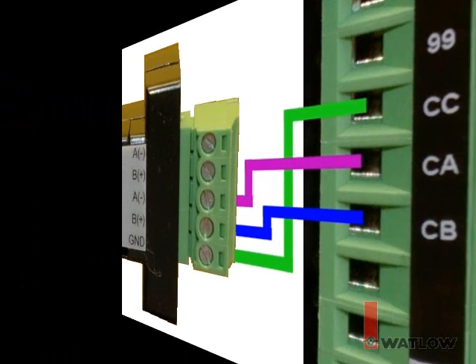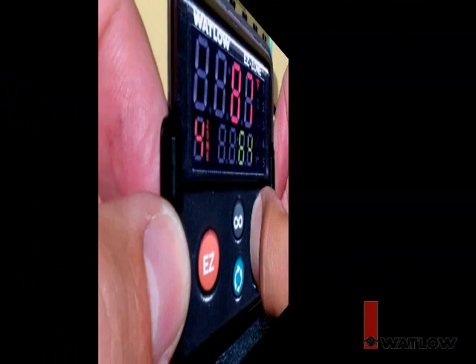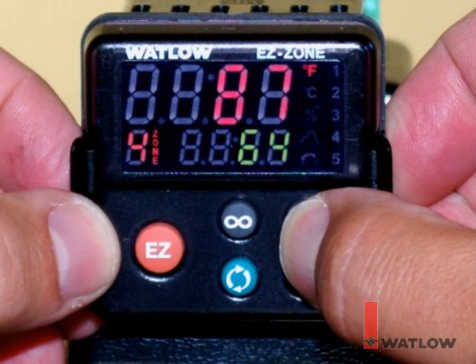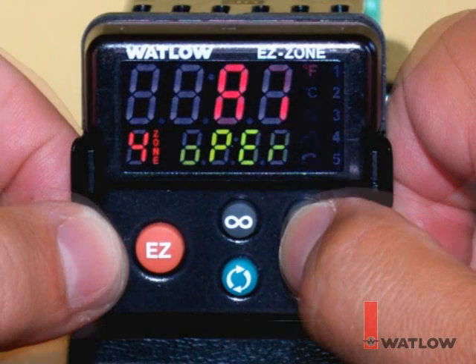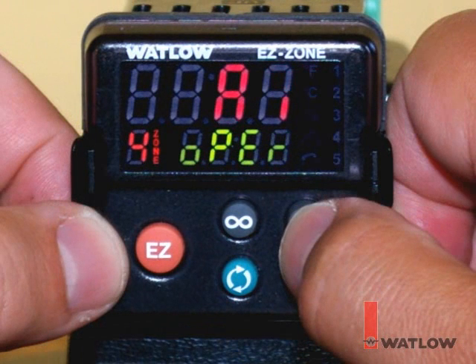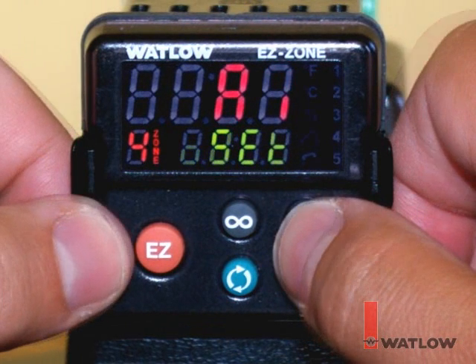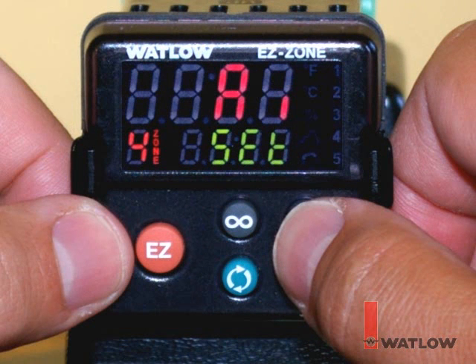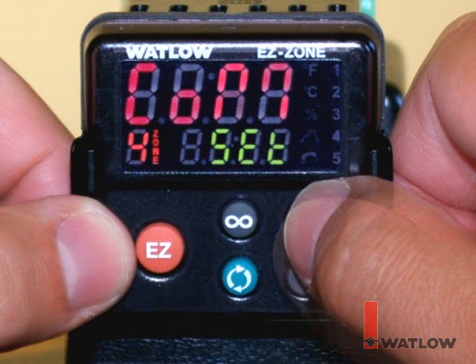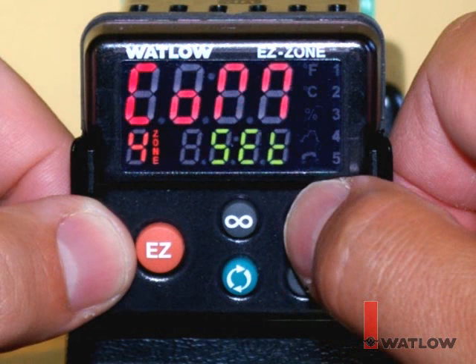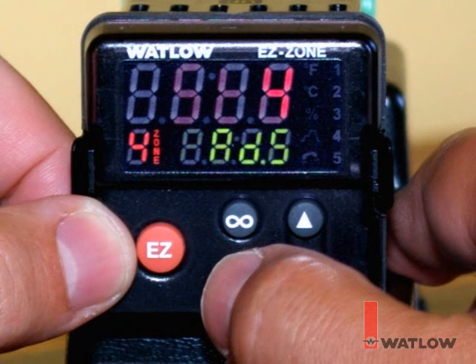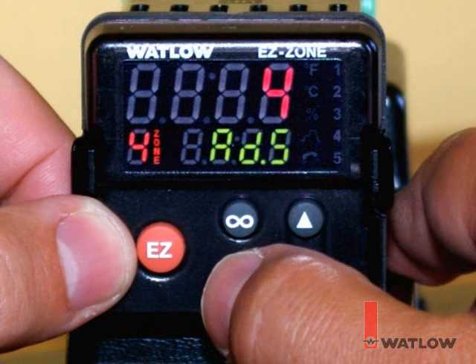Next, let's configure the controller's communications options. Like all EZ-ZONE products, the PM supports the standard bus communications protocol. This model also supports Modbus RTU, so on the setup page's communications menu, I've made sure the protocol is set to standard bus. Also, the PM's standard bus address or zone number is set to 4.